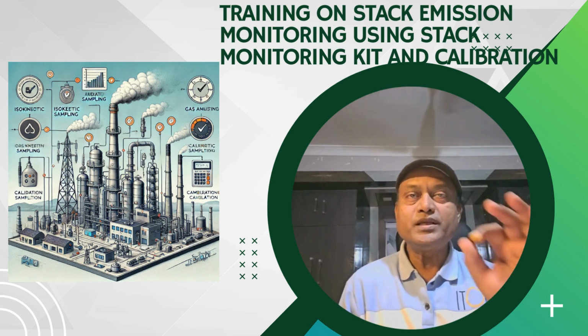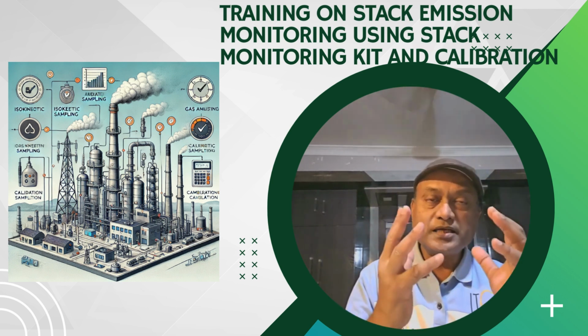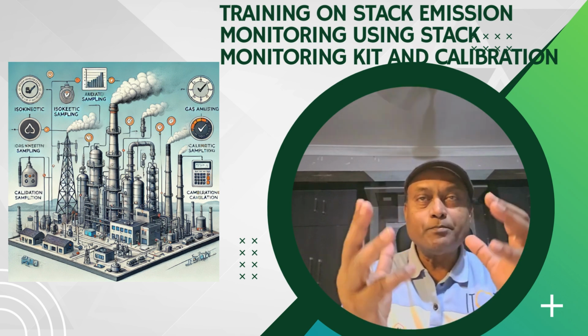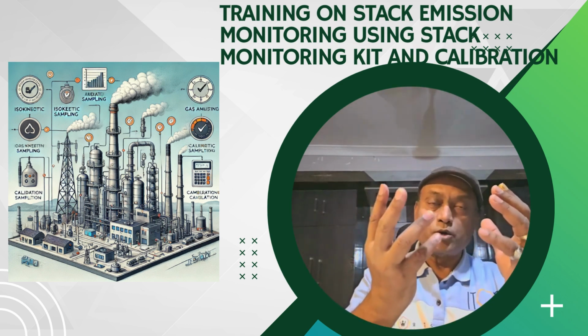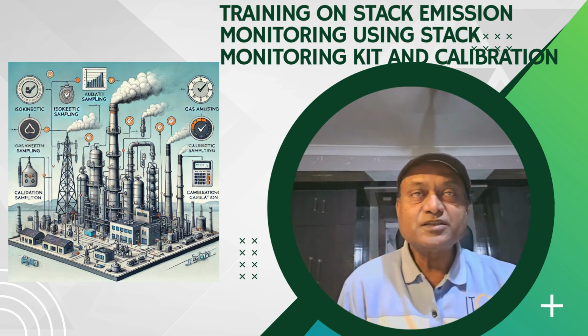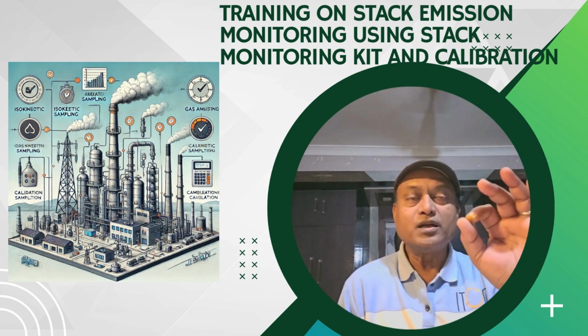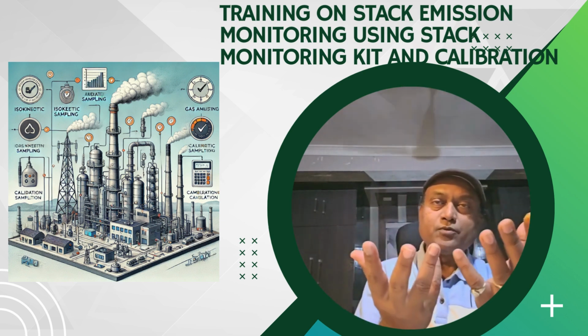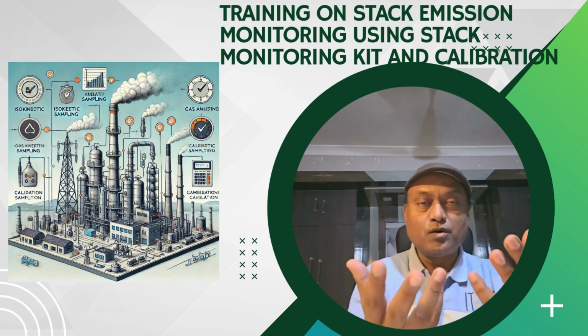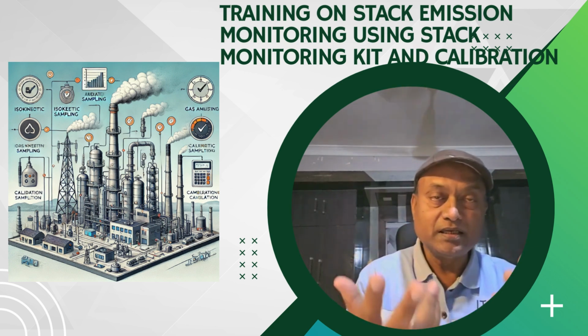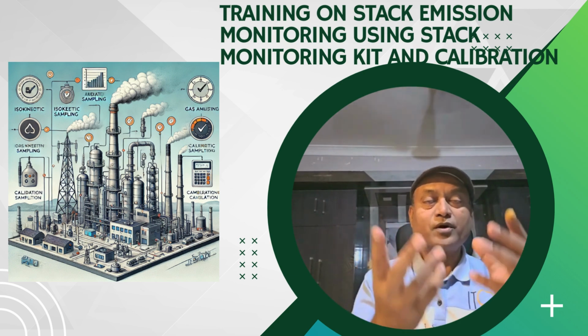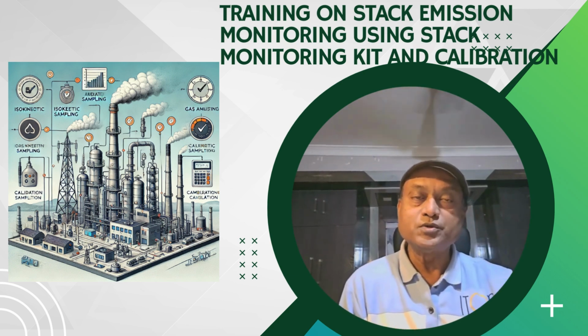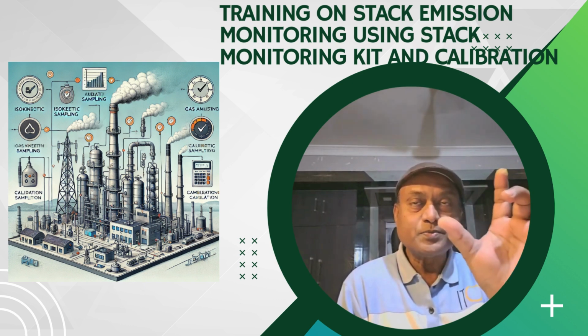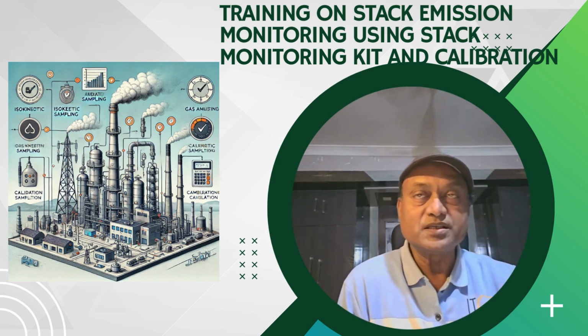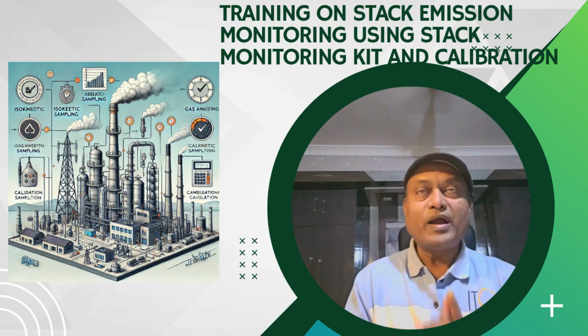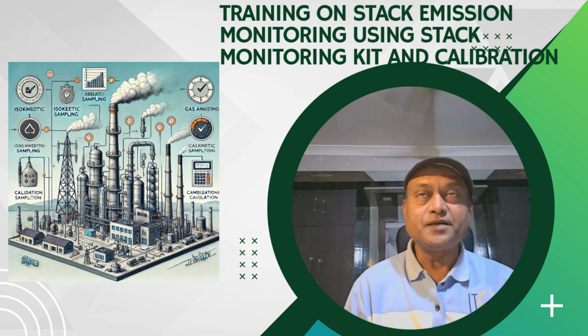Frequency of calibration. Before each monitoring session it should be calibrated, and after major repairs or component replacement calibration is also needed. As per the manufacturer's guideline or local regulations, you have to fix the calibration period, maybe before each sampling, or maybe fortnightly, or when you are going to monitor a very specific kind of industrial emissions.